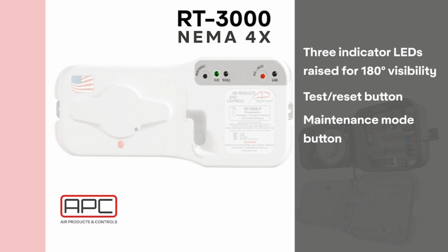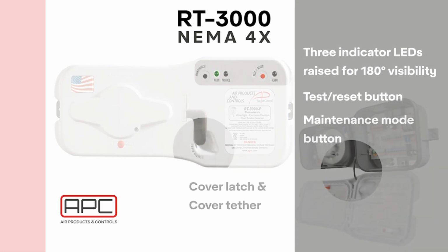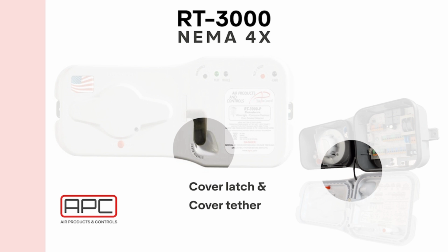The LEDs indicate alarm, pilot, and trouble. The RT3000 has a maintenance mode that offers a 3-minute interval for test and maintenance functions with no extra trouble reports to the system. The maintenance mode automatically shuts off when the cover latch engages or after 3 minutes, whichever is first. For cover removal, there is a latch that releases the cover. Once released, a cover tether holds the cover to the unit.